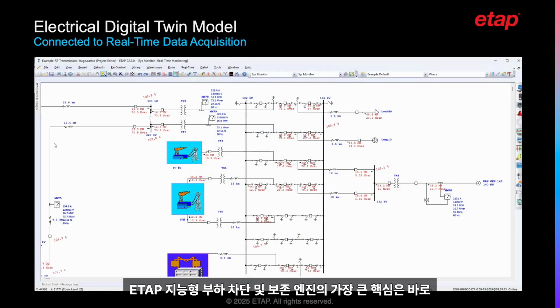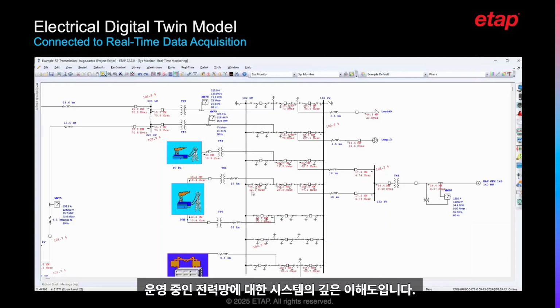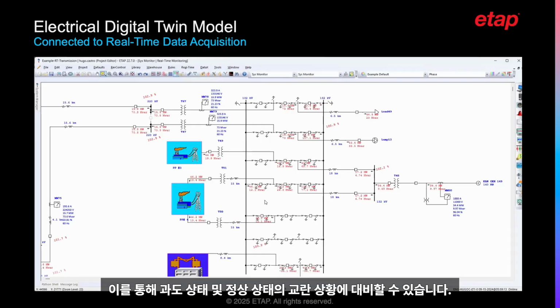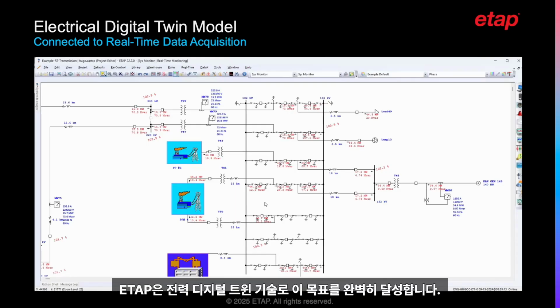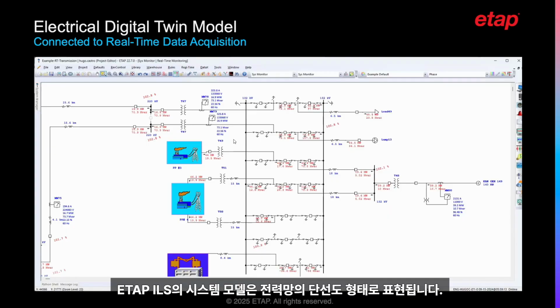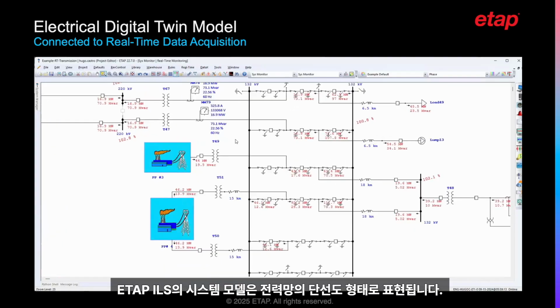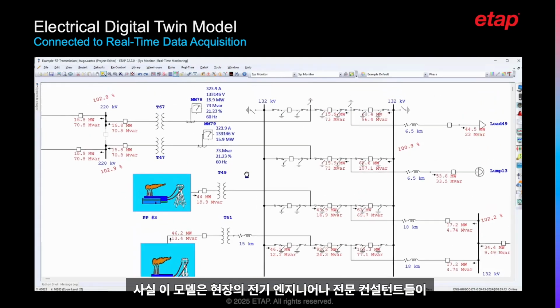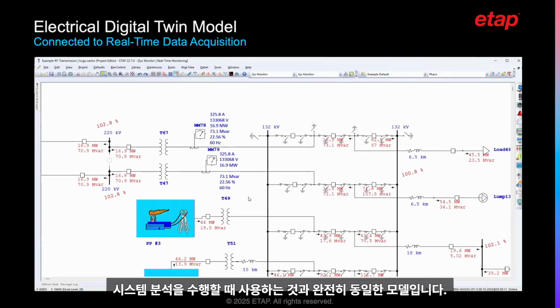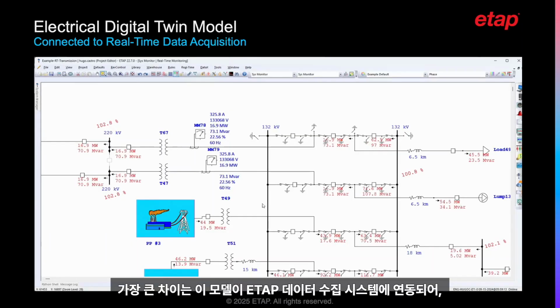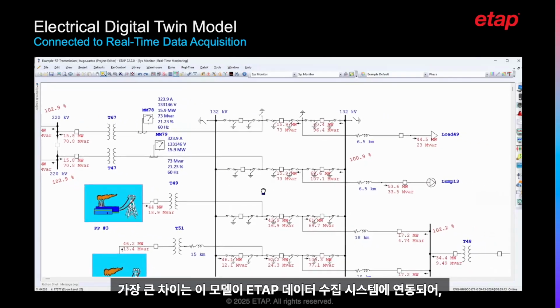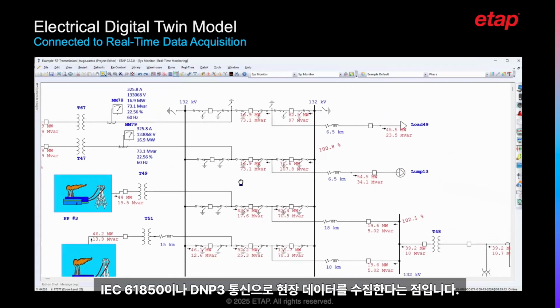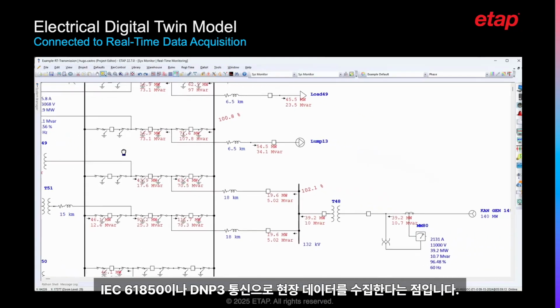The key of the ETAP Intelligent Load Sharing Load Preservation Engine is its understanding of the electrical network. With this knowledge, the load sharing system will be able to accurately predict system response and therefore be prepared for transient and steady-state disturbances. ETAP achieves this by using the electrical digital twin. The system model is represented in the ETAP ILS by the one-line diagram of the system. In fact, this model is the same model utilized by the electrical engineers on site and consultants performing system analysis. The main difference is that this model is now connected to the ETAP data acquisition system, collecting data from the field via IEC 61850, DNP3, or any other protocol.